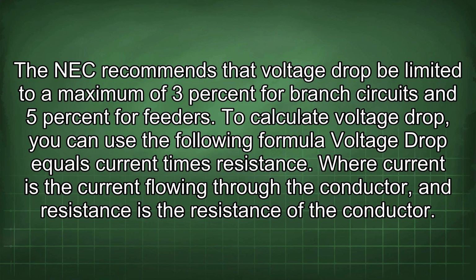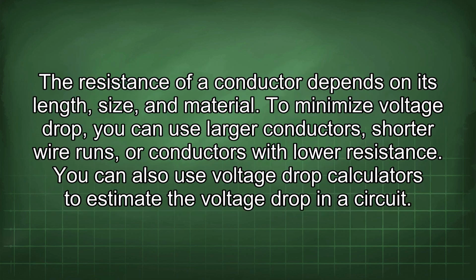To calculate voltage drop, you can use the following formula: voltage drop equals current times resistance, where current is the current flowing through the conductor, and resistance is the resistance of the conductor. The resistance of a conductor depends on its length, size, and material. To minimize voltage drop, you can use larger conductors, shorter wire runs, or conductors with lower resistance. You can also use voltage drop calculators to estimate the voltage drop in a circuit.